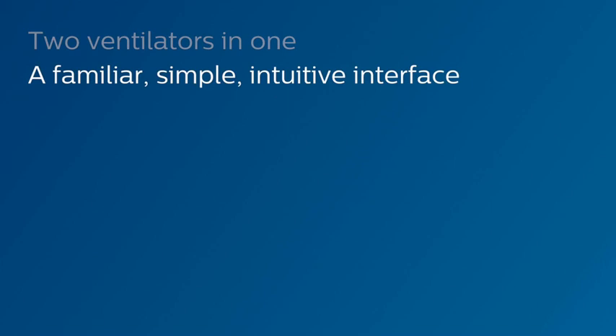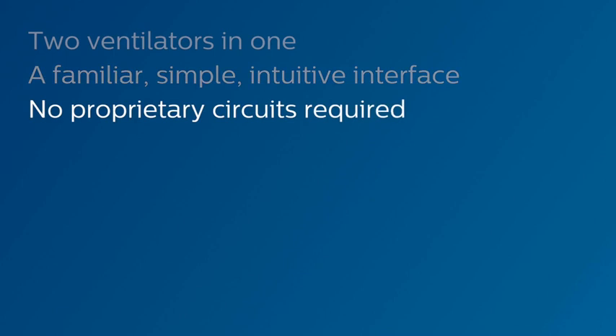No proprietary circuits required. Which means you can save money and inventory space by using your BiPAP circuits for non-invasive and a simple dual-limb circuit for invasive applications.